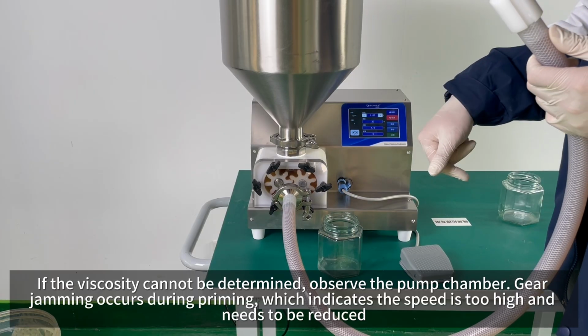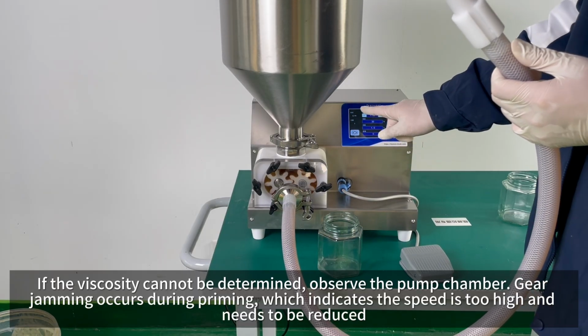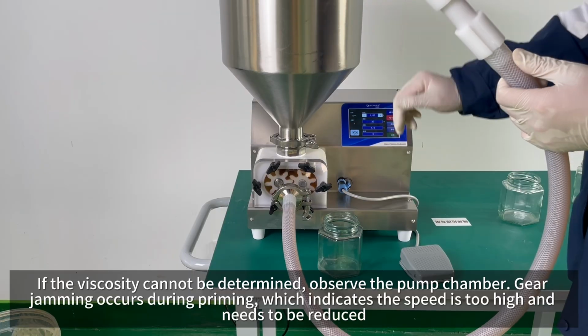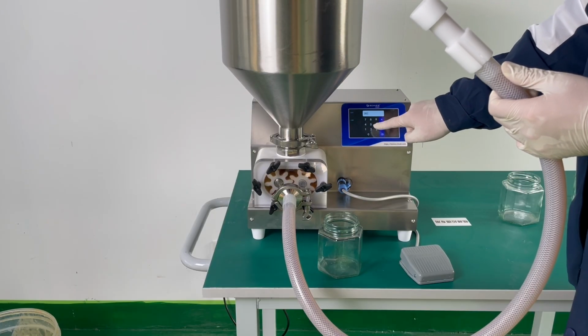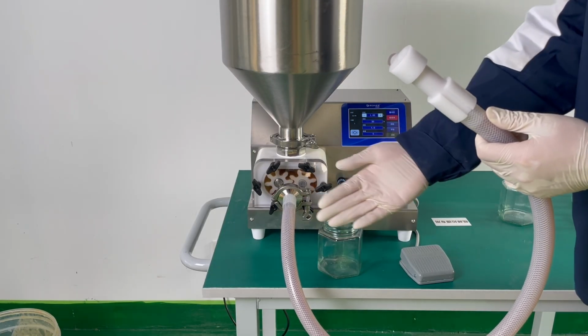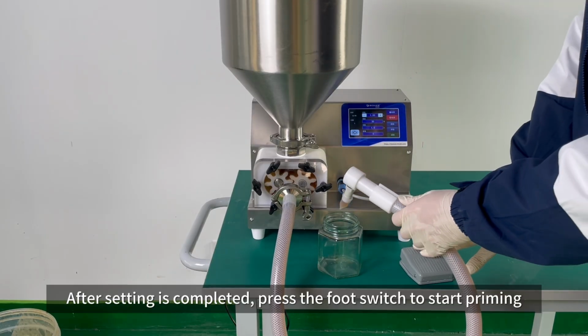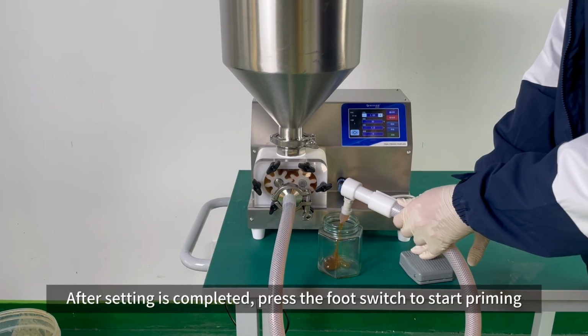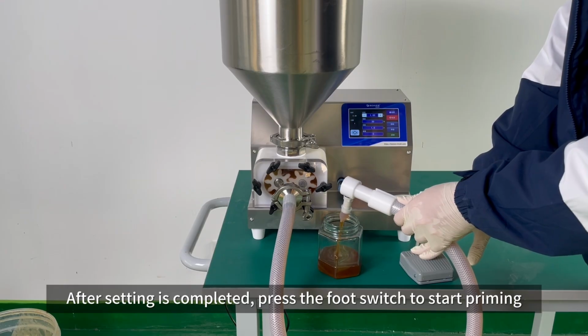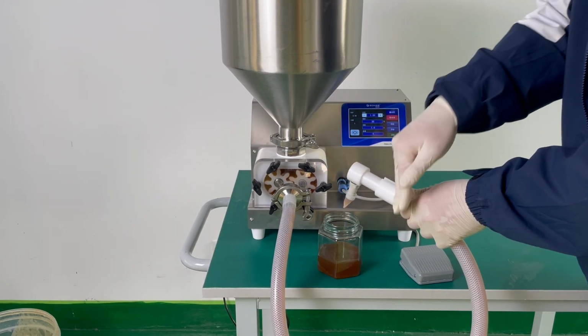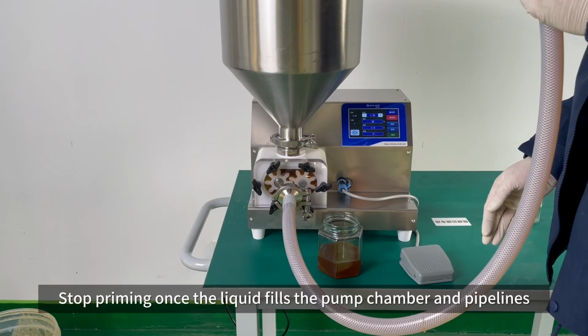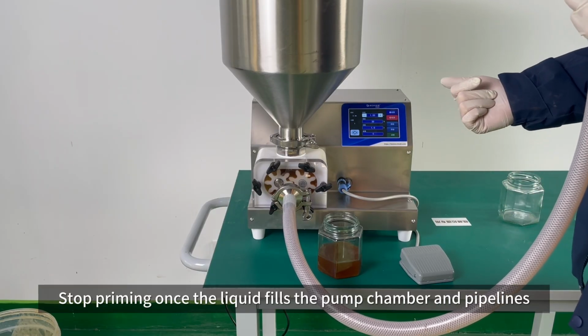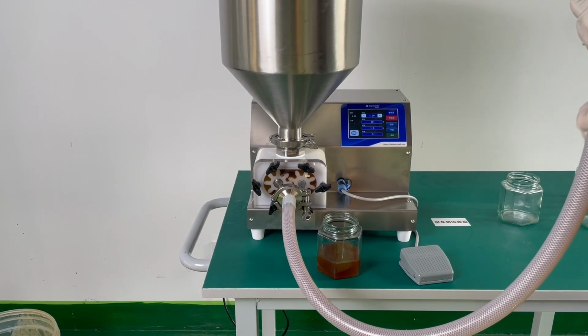Gear jamming occurs during priming, which indicates the speed is too high and needs to be reduced. After setting is completed, press the foot switch to start priming. Stop priming once the liquid fills the pump chamber and pipelines.